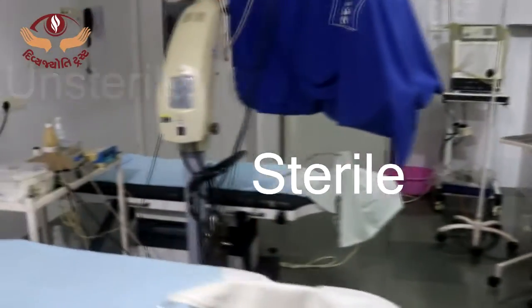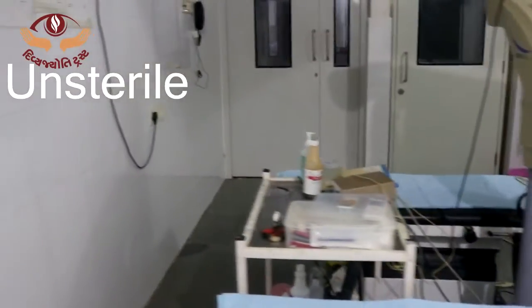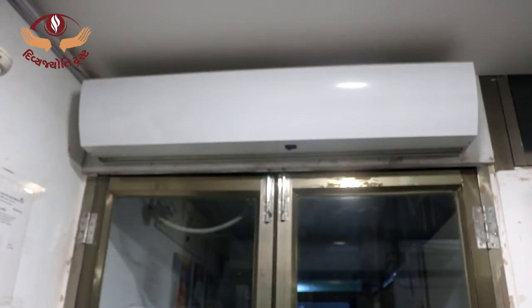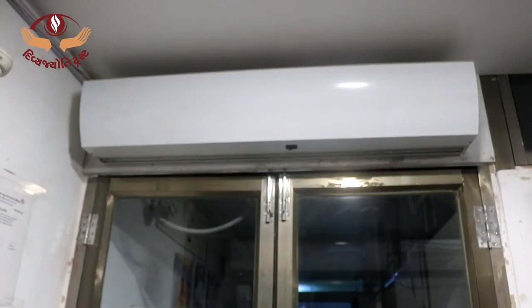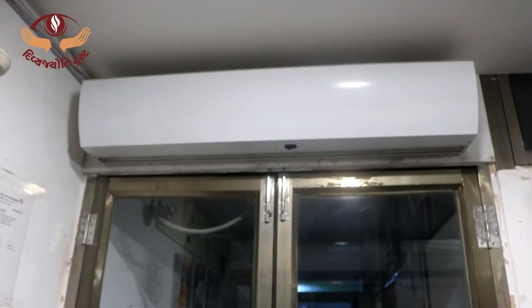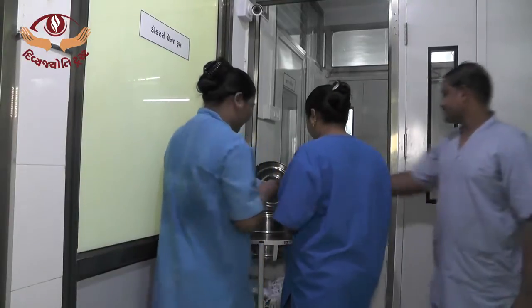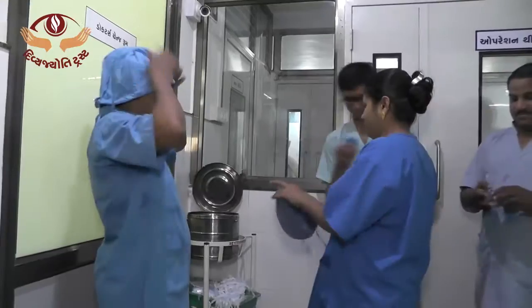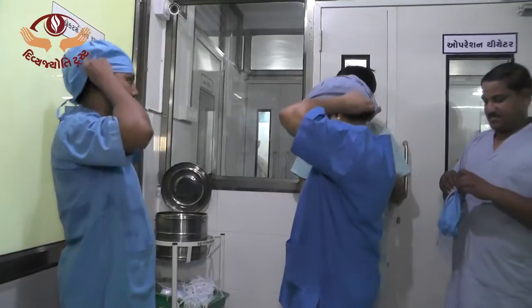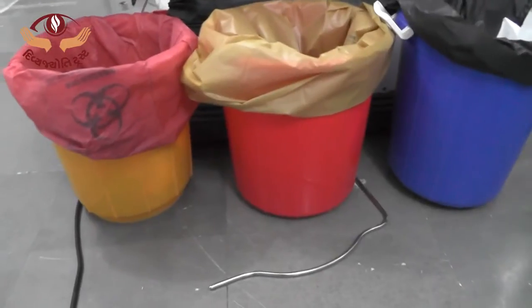Sterile and unsterile areas should be segregated. Airlock to be provided, preferably adding air curtain unless there is positive pressure ventilation. Separate entries for the scrubbed staff and sterile items, and circulating staff, patients and unsterile items and waste disposal. The operation theatre should have full wall glazed tiles with minimum joints and stone or vitrified tiles flooring. Marble being porous material should be avoided.